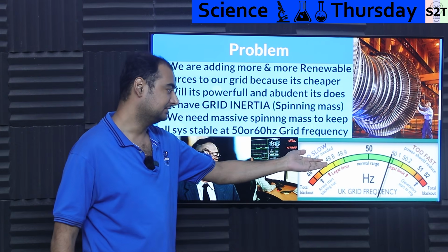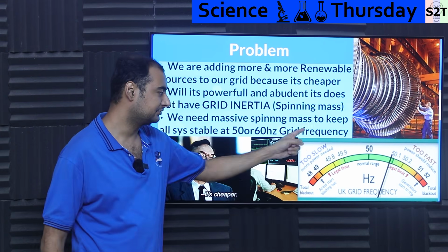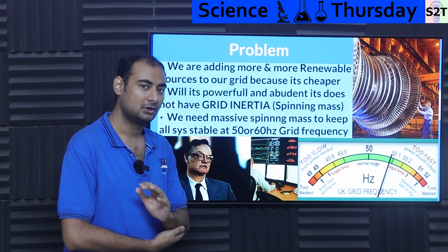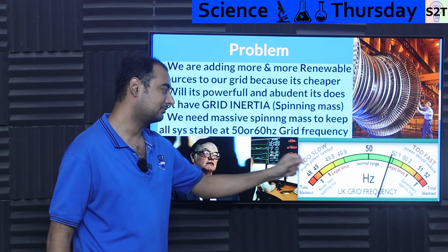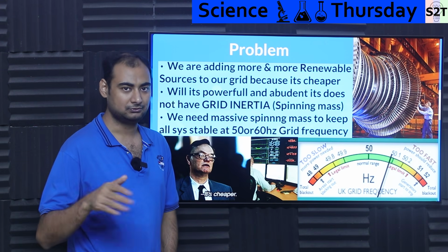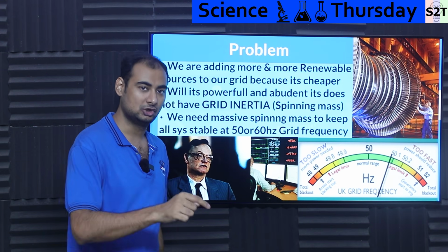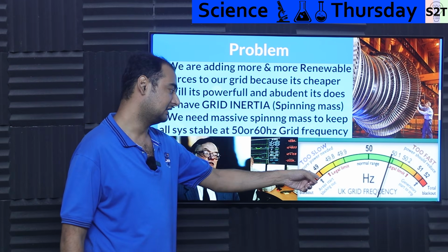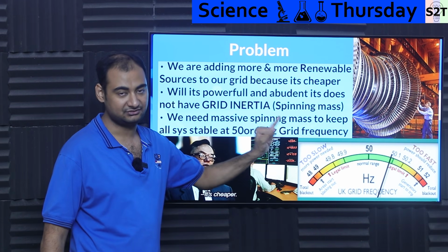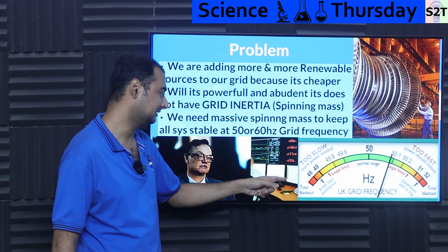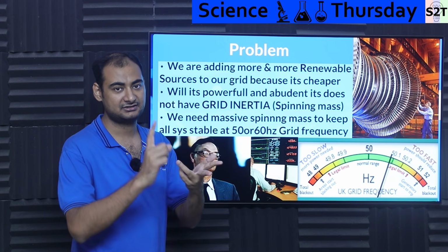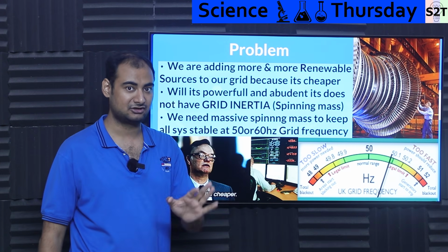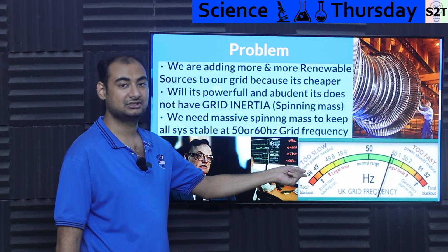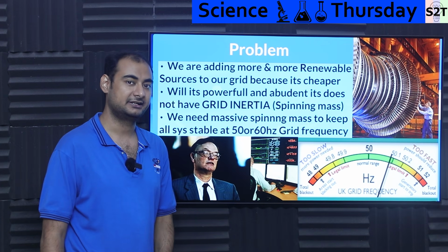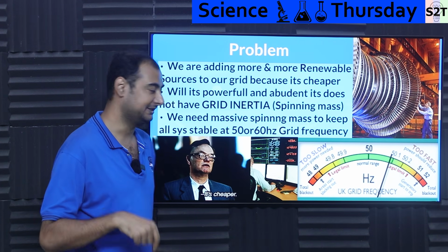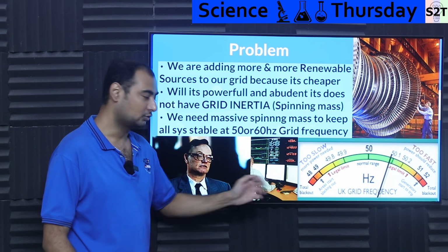The opposite also happens. Let's say you're starting to put more and more load onto it, and it drops to 49.9. People are like, whoa, whoa, whoa. People will start to pay attention. It starts to drop to 49.8. It's like, yo, figure out where we can get extra power or do load shedding. People will start to make phone calls. It starts to reach 49.5, the legal limit. You have to shed loads. You cannot send dirty power, especially to high priority targets like data centers, hospitals, things of that nature. You cannot send dirty power. And then it starts to reach the dangerous zone, which is 49 hertz. Yeah, red alert. You are very close to generators auto tripping. And then 48, same thing, total blackout.